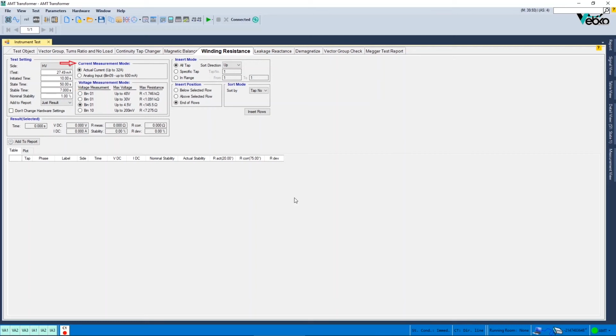The current measurement mode is specified in the current measurement mode section, and if the current is below 0.6 amperes, analog input should be selected, while if it is higher than 0.6 amperes, actual current should be selected. The voltage measurement mode is specified in voltage measurement mode. Since the resistance measurement method divides voltage by the current, the voltage range of the binary inputs affects the measurement accuracy. Therefore, it is necessary to select one of the inputs of this section for measurement, based on the winding resistance and the maximum resistance specified for each binary input.